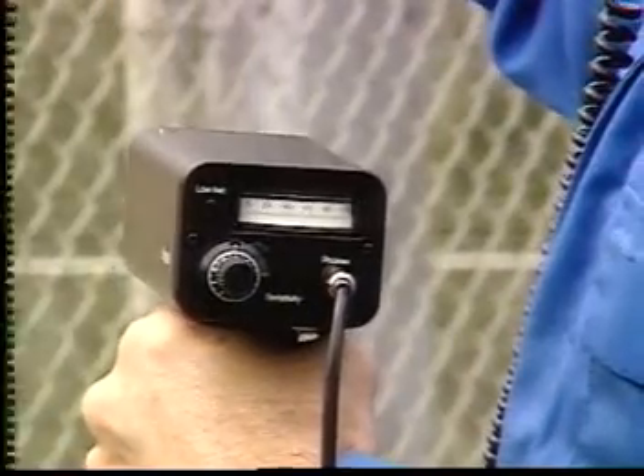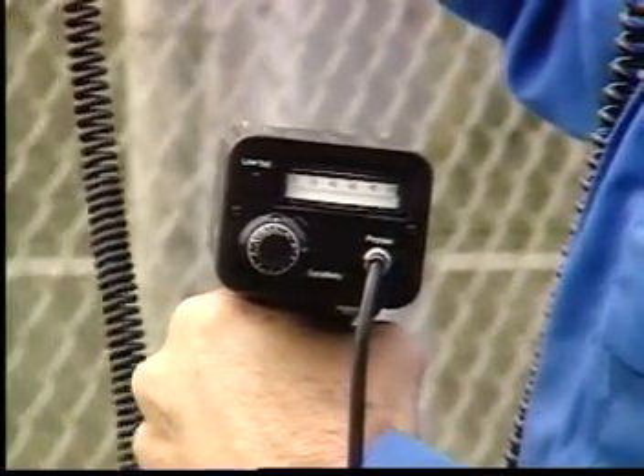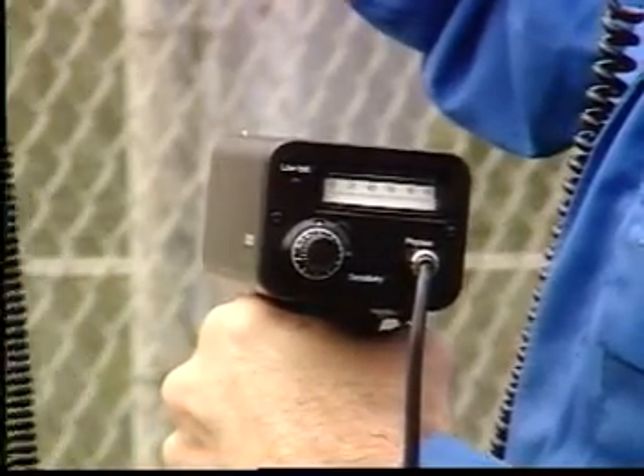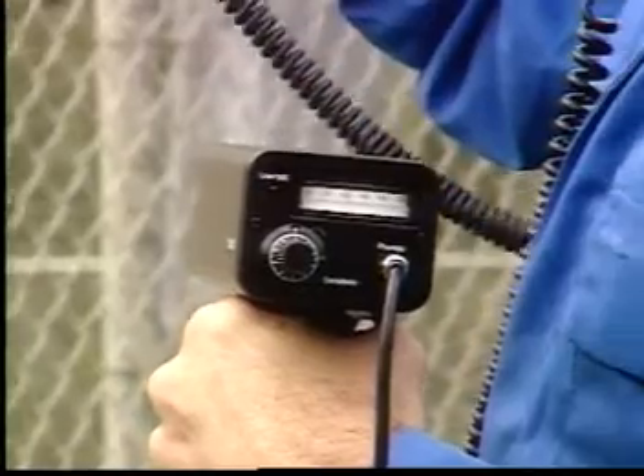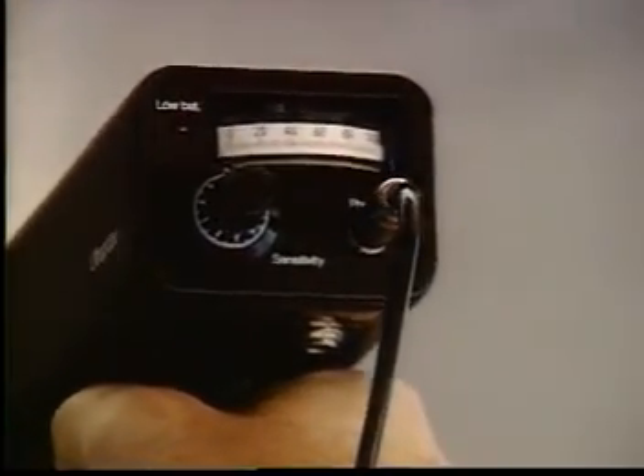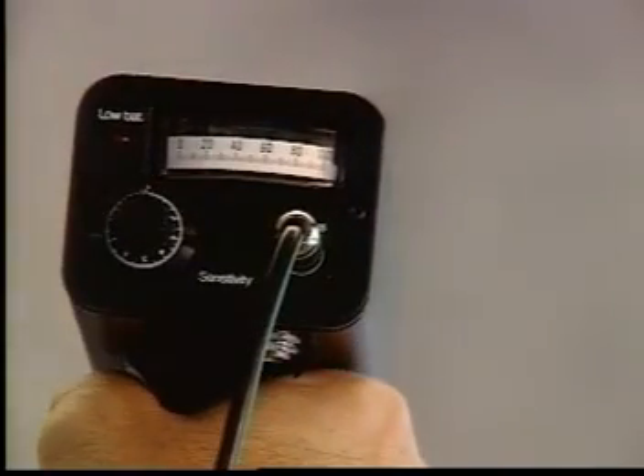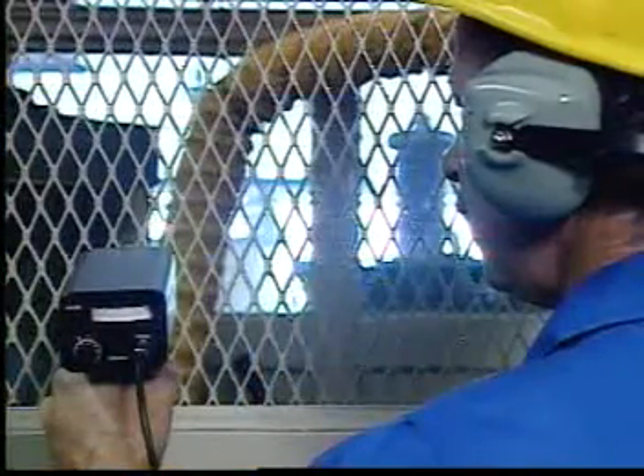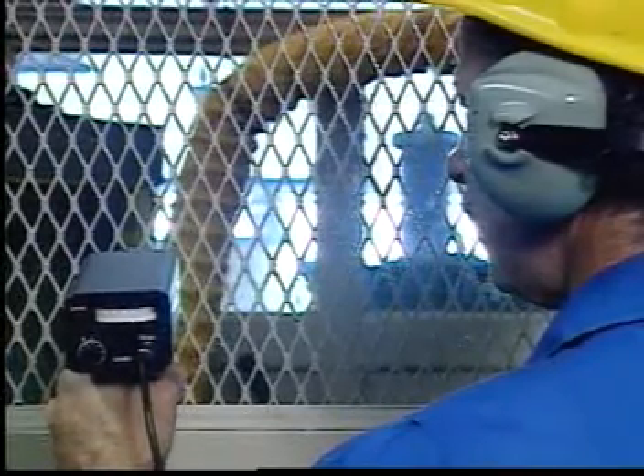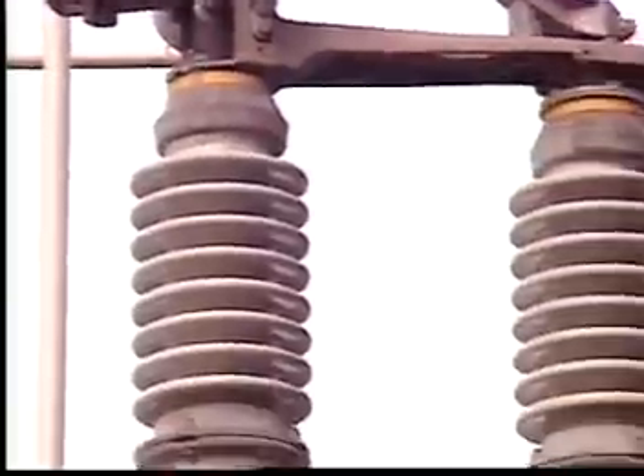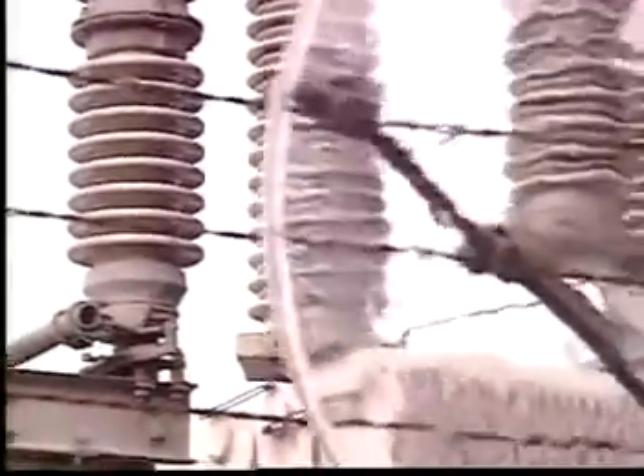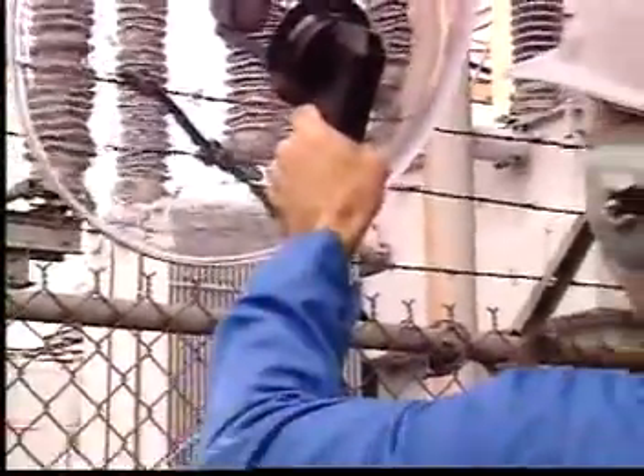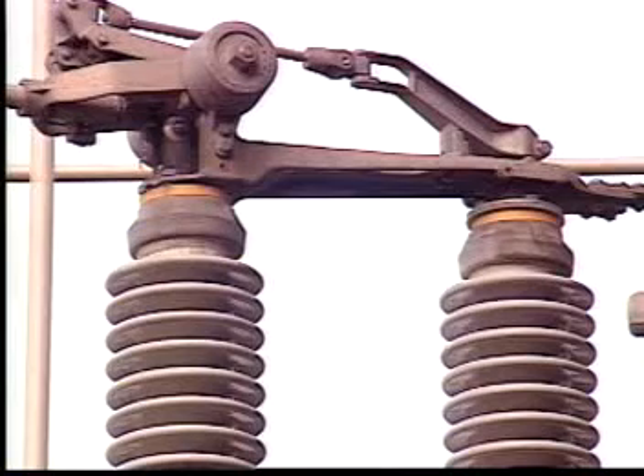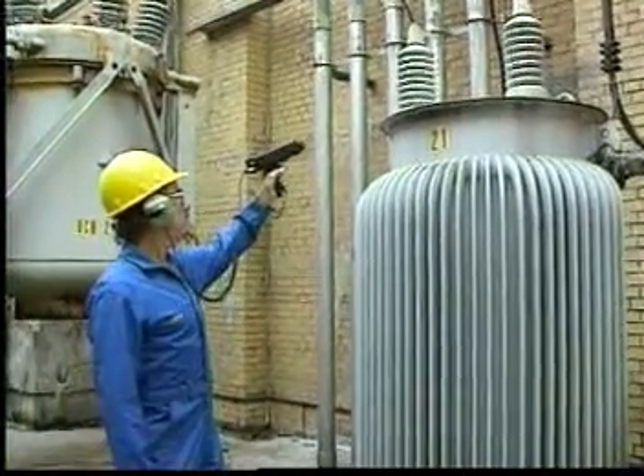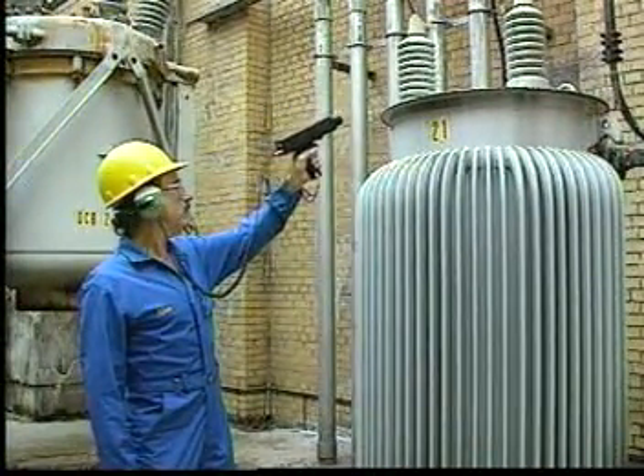An intermittent sound indicates destructive corona. A continuous sound indicates nuisance corona. Experience and familiarity with your equipment will make diagnosing problems easier. Due to the nature of the phenomenon, there are no exact standards to predict what meter readings will indicate whether you are experiencing real or nuisance corona. The best testing method is to compare the sound quality of areas of similar material and function. Listen for differences as you visually inspect them and make notes for future comparisons.